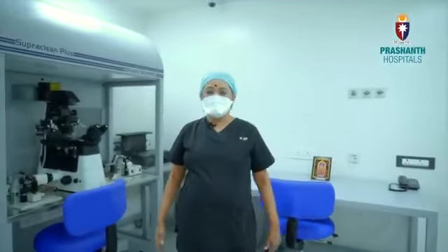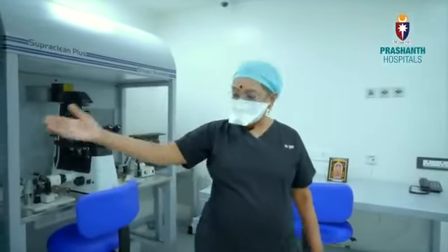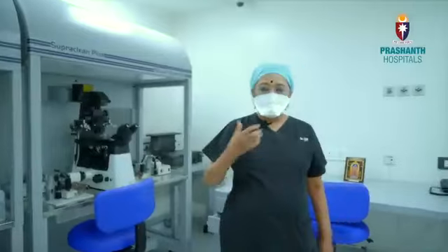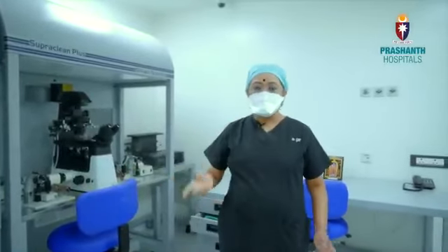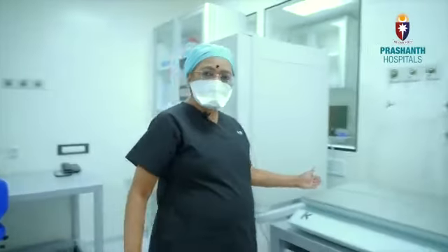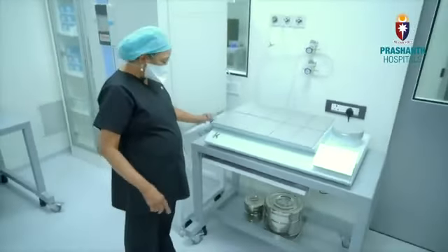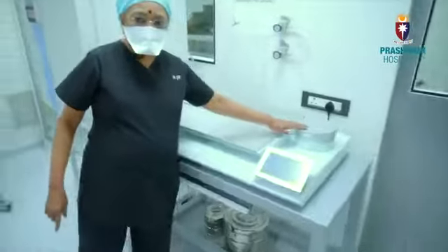Now it's important to tell you about the air systems in this IVF lab. Now we have what we call a HEPA filter, which actually is the first filtering system. So this is the HEPA filter. It's actually the first filtering system which filters all the abnormalities, and this is incorporated in the air conditioning system. Now the second level of filtering is called the CODA filter. The space is going to be there, and the CODA filter absorbs the rest of the impurities. Now once again, the third filter is the charcoal filter, which is fitted in the incubator. So this is the charcoal filter which is actually fitted in, and the humidity inside is maintained with this humidifier, so that all the things are maintained in perfect condition.